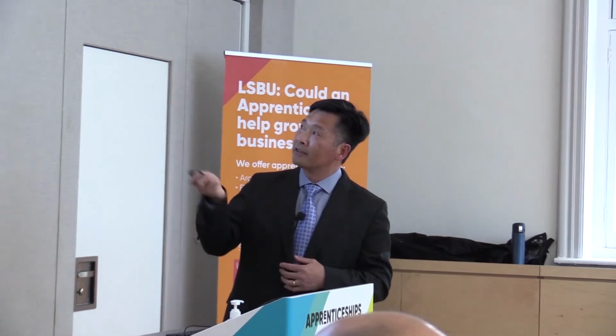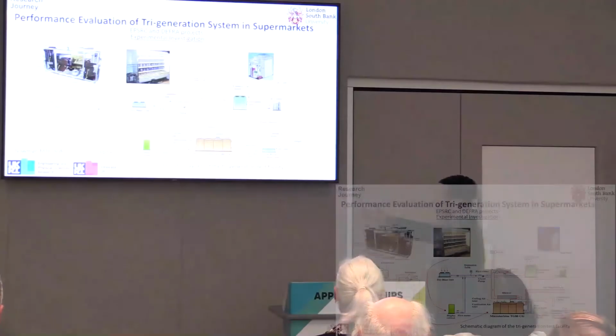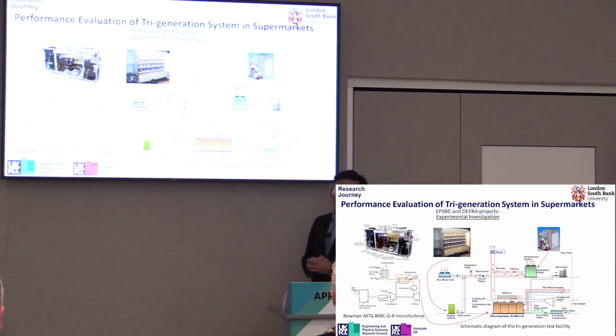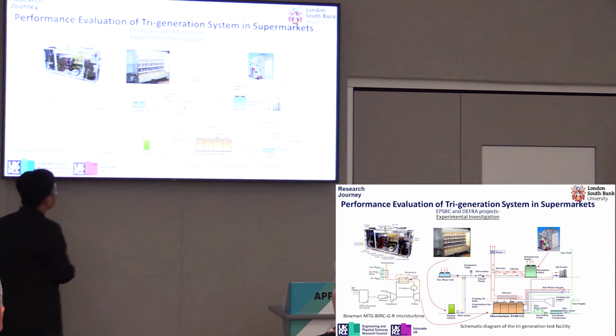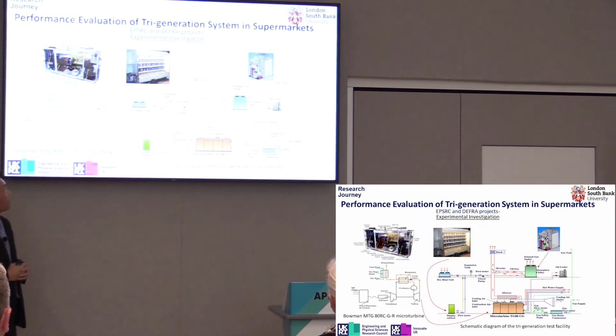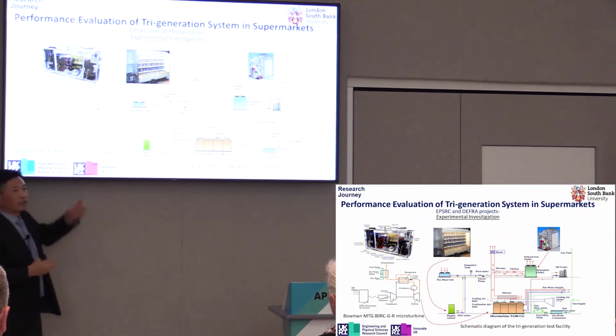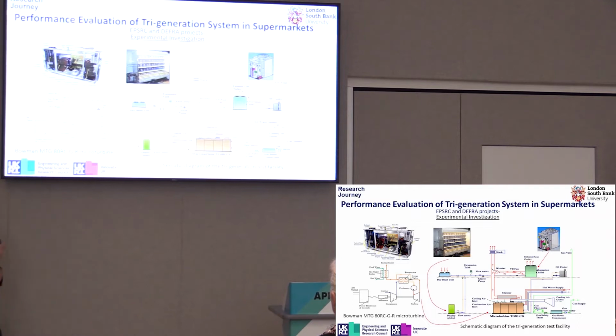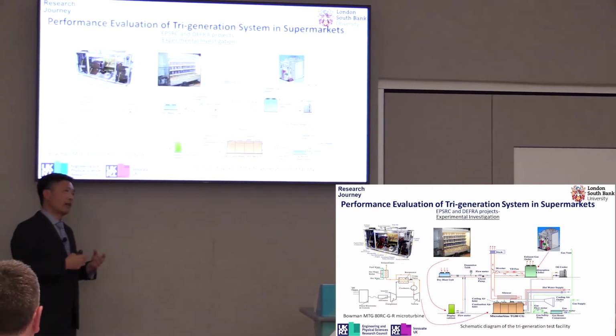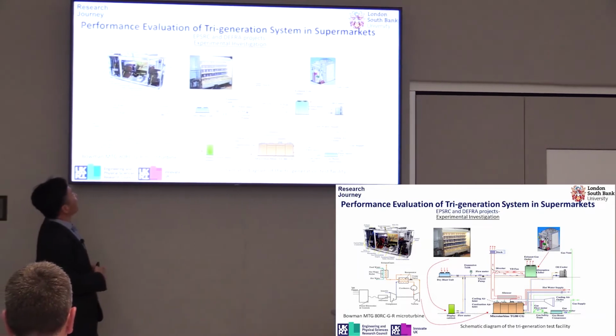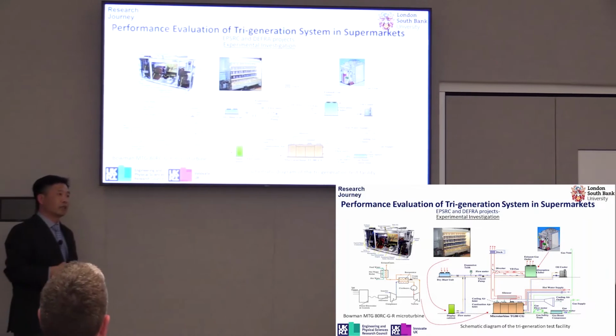This test system consists of a number of main components. One is the 80 kilowatt micro turbine generator. You see here the internal structure of the micro turbine generator. It has an air compressor and a gas turbine, and also a recuperator to enhance the efficiency of the micro turbine generator. And it has a combustor, where a mixture of fuel and air is burned and generates power. And then it has an integrated hot water heater to produce heating.